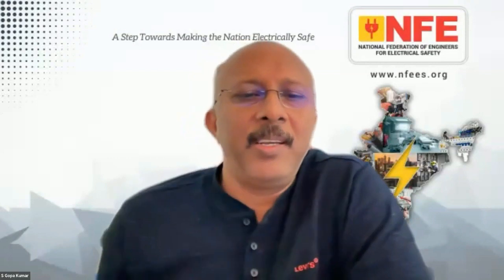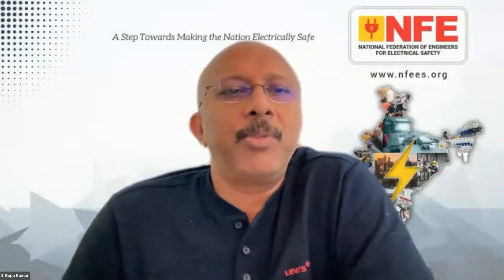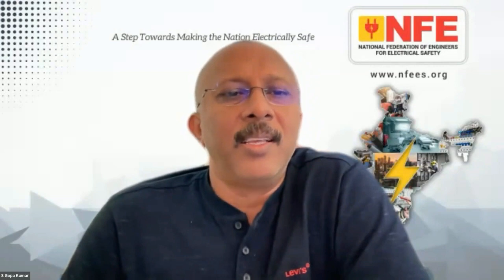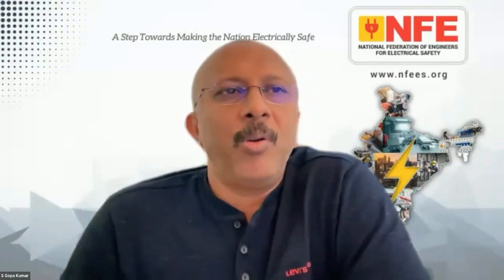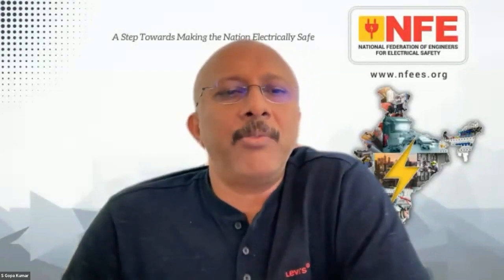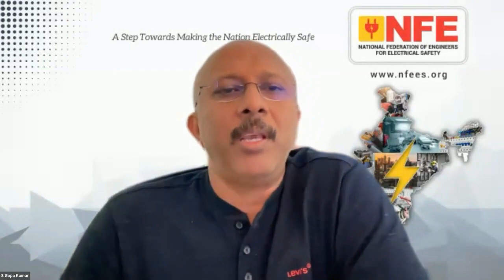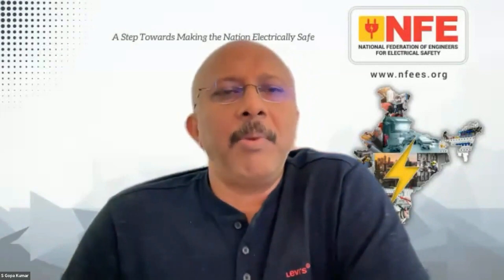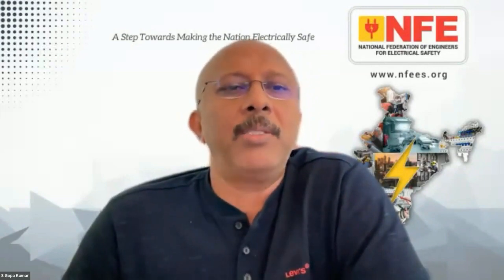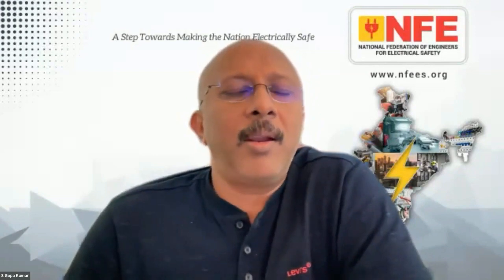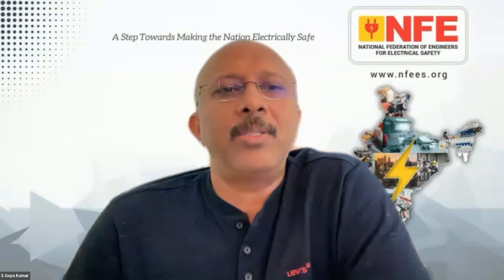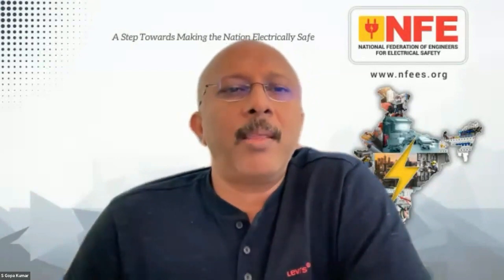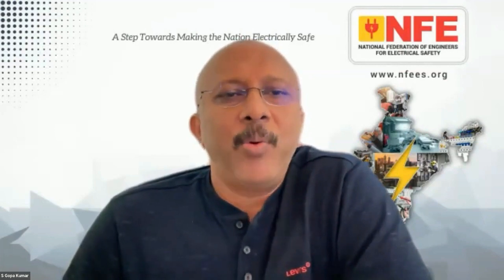Actually, in India, this is a big issue because most of the time we have the habit of using non-standard products. As a result, the leakage currents are much more. Also, sometimes I come across this situation, especially with variable frequency drives and places where semiconductors are used. The leakage currents are much more, sometimes 200, 300 milliamps and sometimes even in amperes. And we also have a funny device sold in the market called a digital grounding device. It's a black box, and these make a short circuit between neutral and earth inside the installation or closer to a machine. Over to you, Mr. Paul.